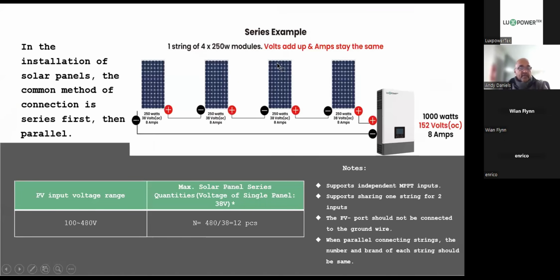So on the PV side, remember we spoke about we can have installations with a string. Here we're looking at a string that is in series, right? So this is one string. Here we have 4 panels. In this example, the panel is 250 watts. The 4 of them give us 1,000 watts. The open circuit voltage is 152 volts, and it's 8 amps. Remember that when you connect in series, voltage goes up, amps stay the same.